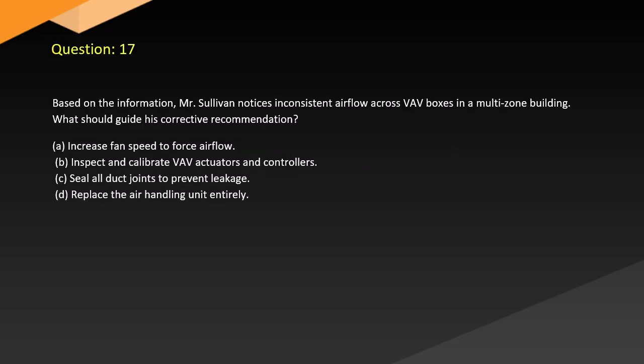Question 17. Based on the information, Mr. Sullivan notices inconsistent airflow across VAV boxes in a multi-zone building. What should guide his corrective recommendation? A. Increase fan speed to force airflow. B. Inspect and calibrate VAV actuators and controllers. C. Seal all duct joints to prevent leakage. D. Replace the air handling unit entirely.